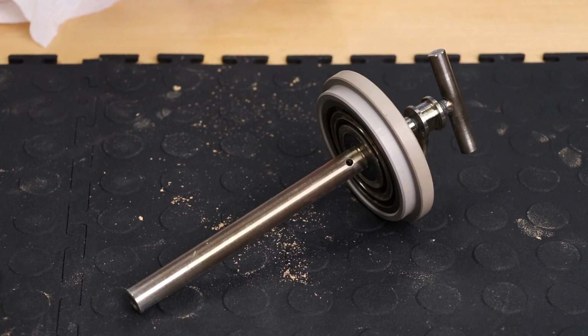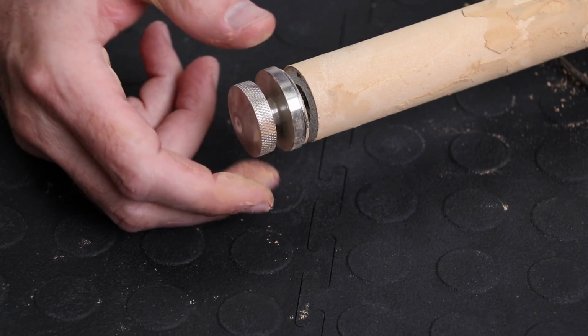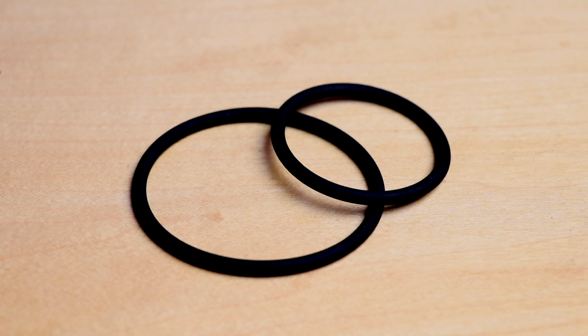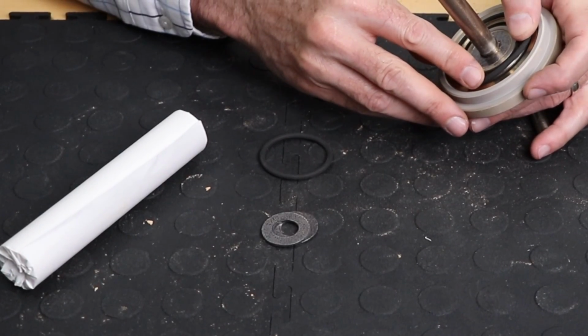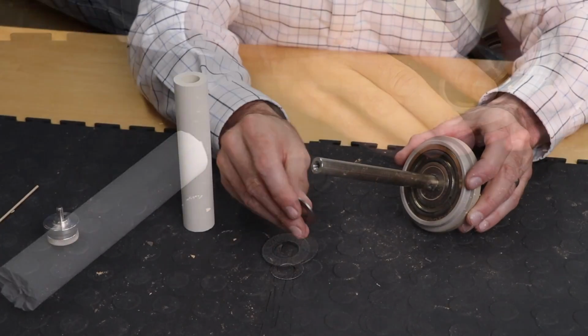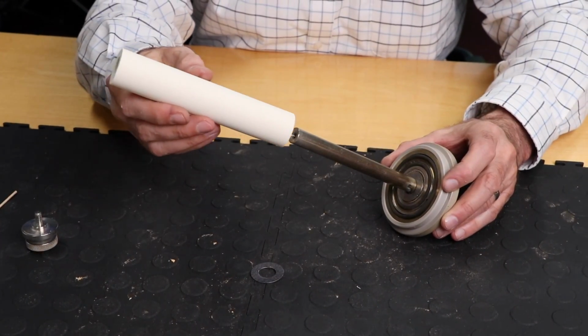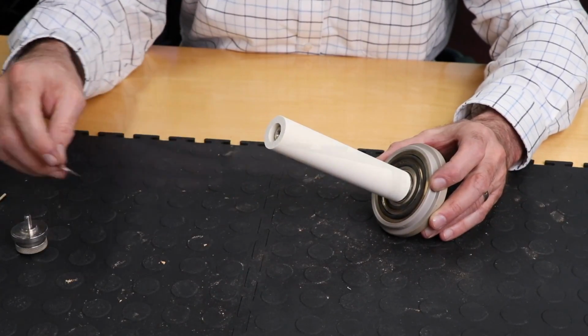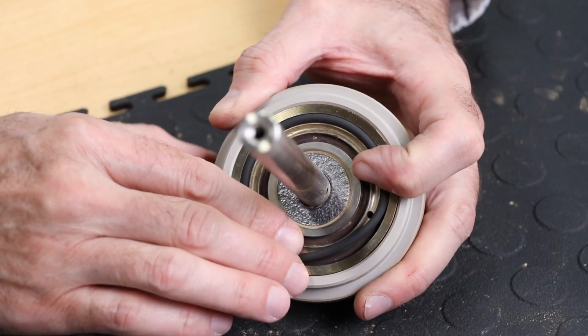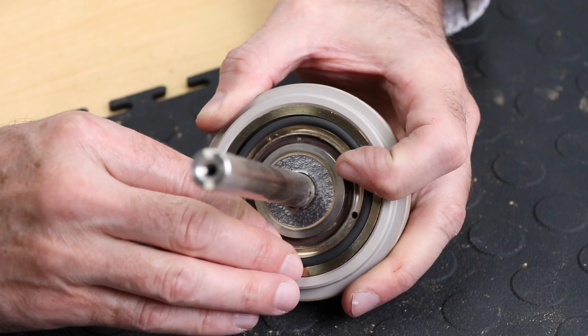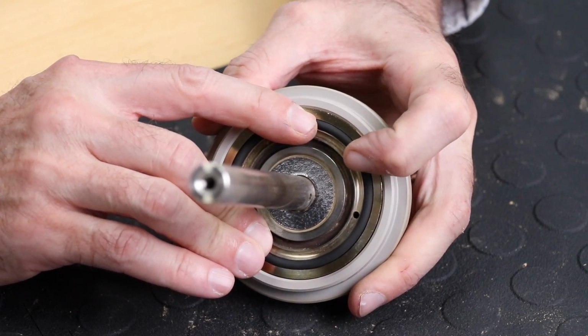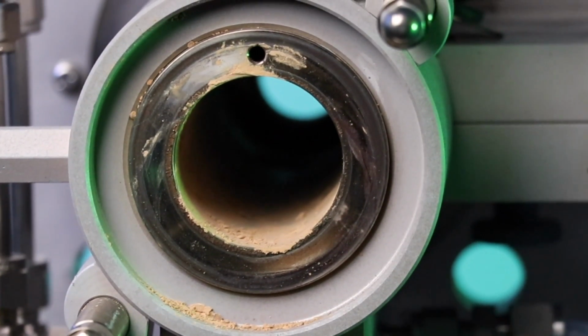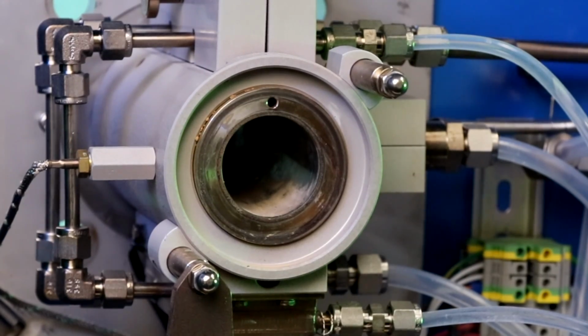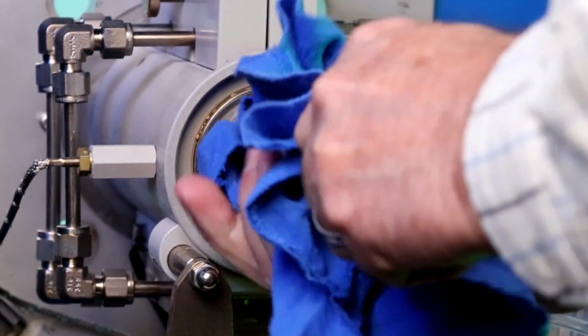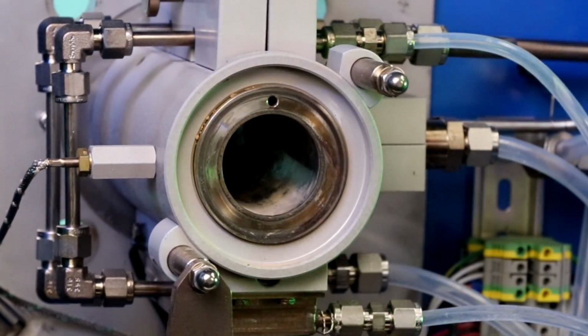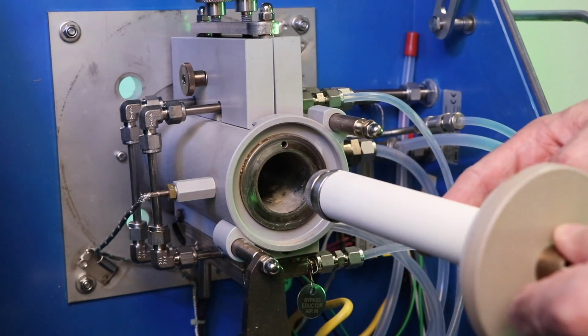The lid assembly includes the filter lid, the knurled knob, the ceramic filter, 2 O-rings, and 2 filter gaskets. Inspect the filter element, O-rings, and gaskets and replace if necessary. Inspect the filter chamber and clean with a damp cloth. While you have the probe open, it is also a good idea to shine a flashlight down the filter chamber and ensure that the probe tube is still extending out into the stack or duct.